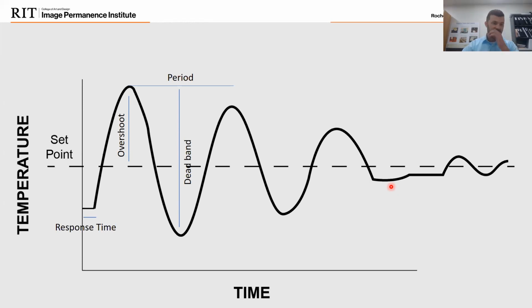Kelly does bring up a good point, I apologize. The tighter the deadband, the less energy efficient we are. We've seen some institutions recommending 2-degree deadbands. It's really tight. I believe the DOE, Department of Energy, was recommending at least a 4-degree deadband. So just keep in mind, the tighter that band, the more energy you're going to use to hold it.